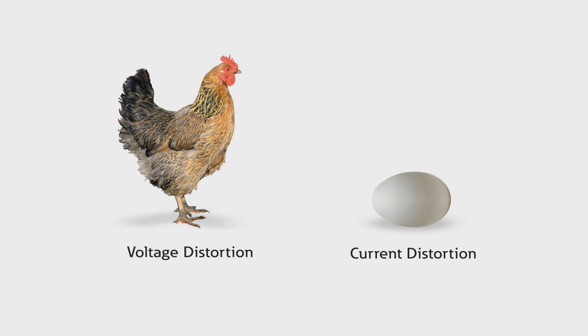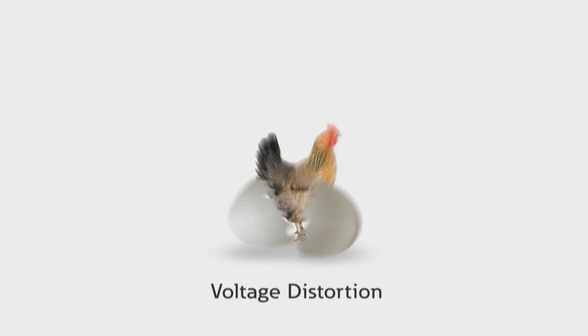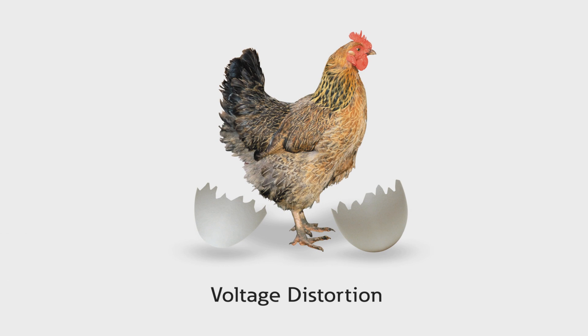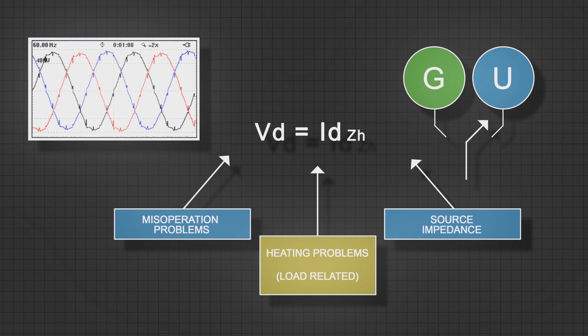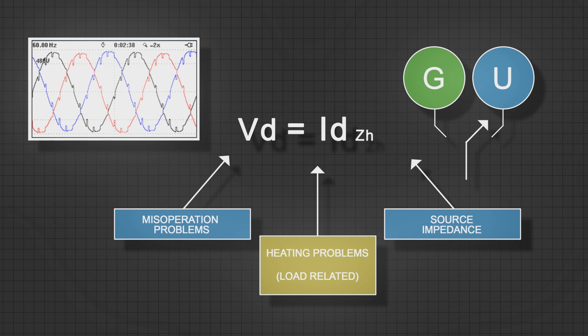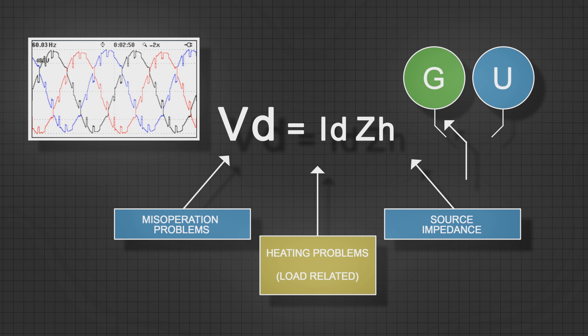So what causes what? Harmonic currents cause harmonic voltage distortion. The amount of voltage distortion depends on how much current distortion is produced — how many non-linear loads like VFDs, computers, or other electronics you have — and the amount of impedance upstream of that current. Usually the most significant impedance is in the nearest upstream transformer, but can be increased significantly when operating on a generator.